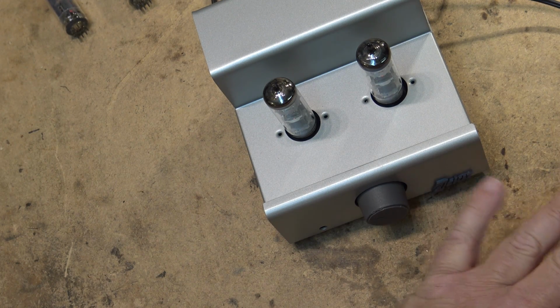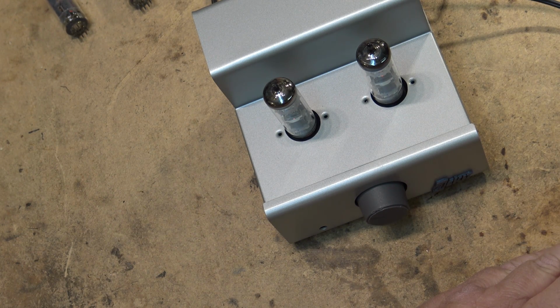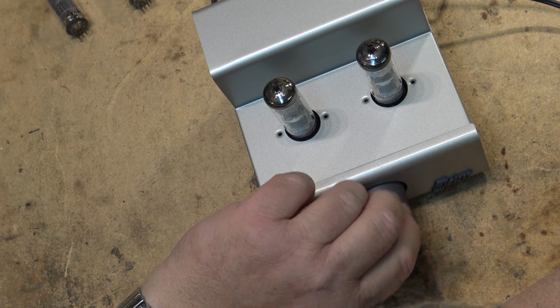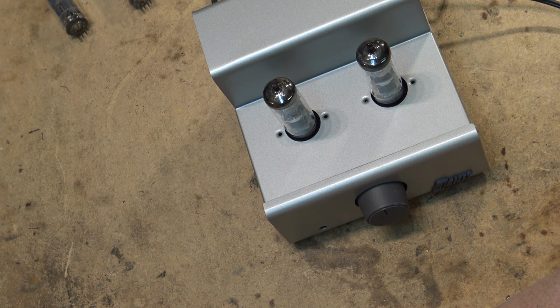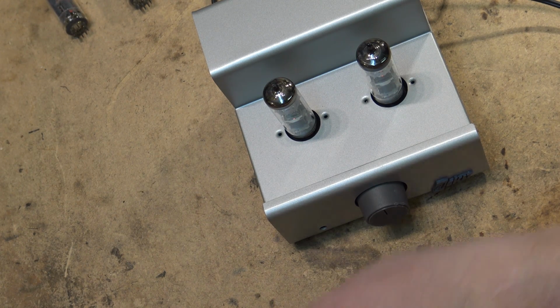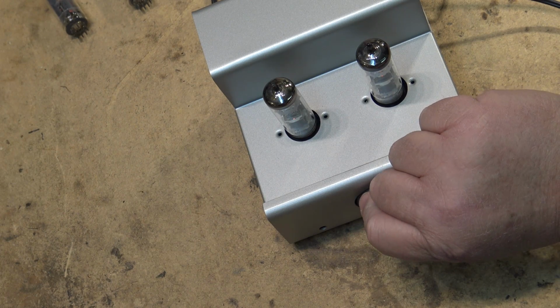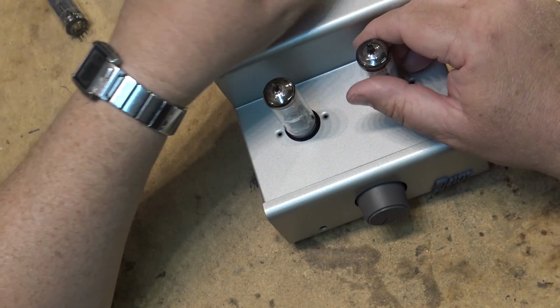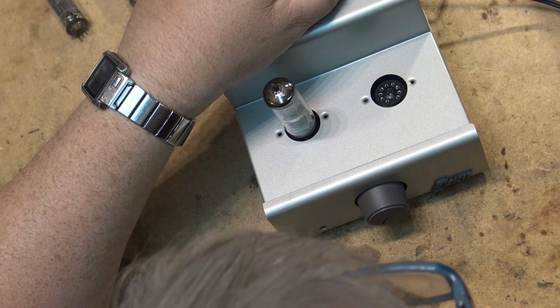Now my tubes are very old, they have tons and tons of hours on these ones. Okay, so we got the same fault. The high voltage is shutting down to the tube, so we know it's not a tube related problem.